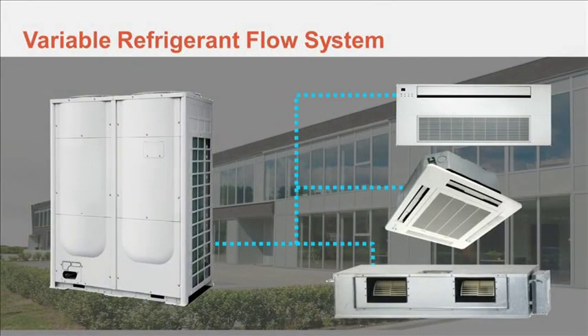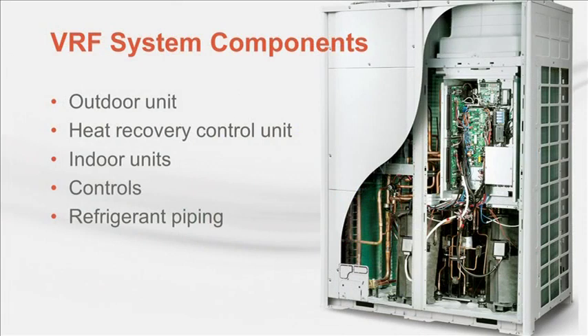Before we get into the application challenges, let's start with an overview to make sure everyone understands what a VRF system is. A VRF system is simply a direct expansion air conditioning system that connects multiple indoor units on a single refrigerant circuit. The indoor units are often in or very near the spaces they're designed to condition, so there's little ductwork, if any at all. There are cooling-only systems, heat pump systems, and heat recovery systems. The latter two are able to provide heating. VRF systems include an outdoor unit, a refrigerant control device for heat recovery systems, indoor units, controls, and refrigerant piping. We'll talk about each of these in greater detail throughout the broadcast.